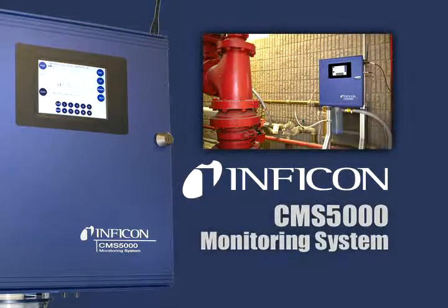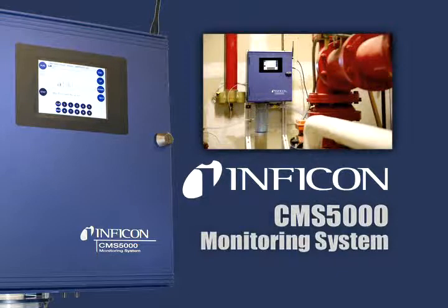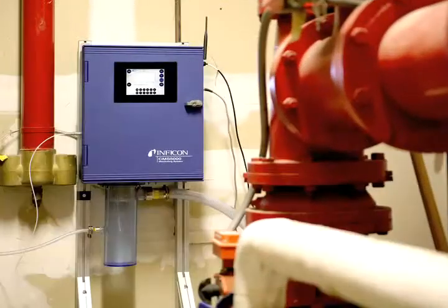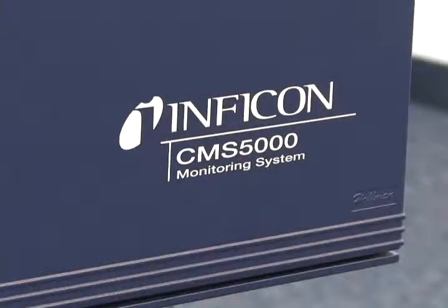The CMS5000 is an online water monitoring system that uses gas chromatograph technology for separation of analytes and a micro-argon ionization detector for the identification of volatile organic compounds, VOCs, in water. The CMS5000 is a stationary instrument that can be wall-mounted or fixed on a stand. The instrument is designed for continuous, unattended long-term monitoring.